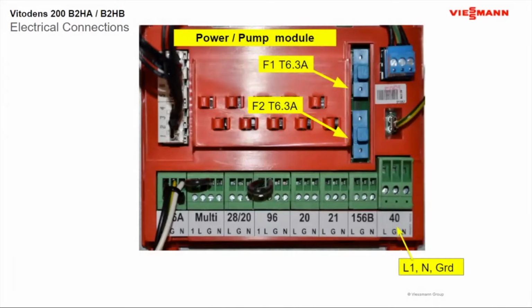And then on the other side, you'll see it's going to be your lower voltage or your communication to the boiler. So with the 200, you do have to wire in the pump underneath the boiler, and it always goes on the right-hand side of the boiler, pumping into the boiler. That's the way we activate that flow switch or the flow sensors. So if you put it on the supply, sometimes it may work, but most of the time it does not work. So always your pump goes on the right-hand side of the boiler, facing it, pumping up into the return side of the boiler. The 21 pump is always designated as your domestic pump or going over to an indirect. But in coding, you can change that to be a heating pump as well.